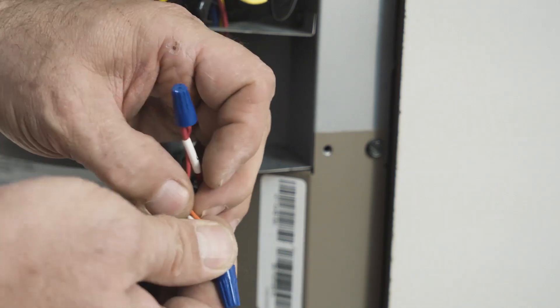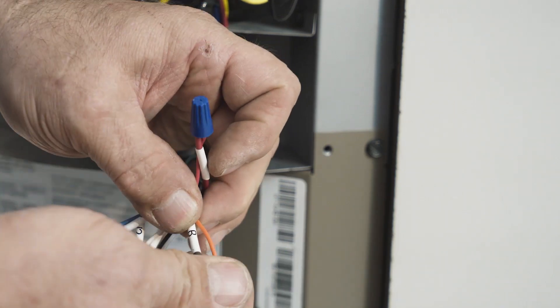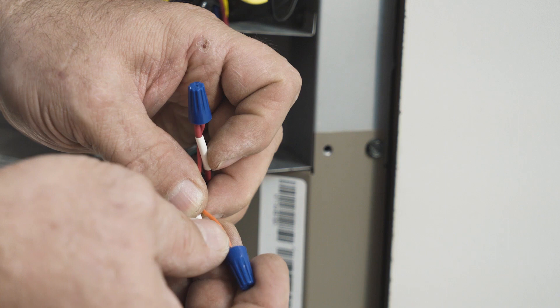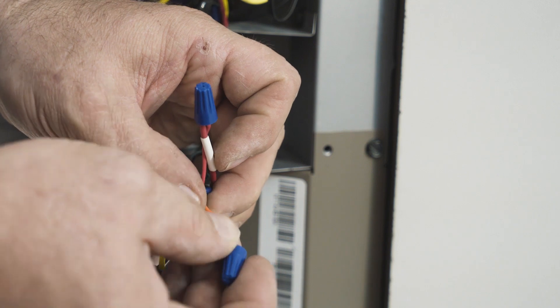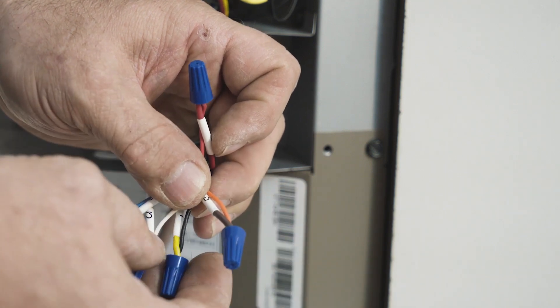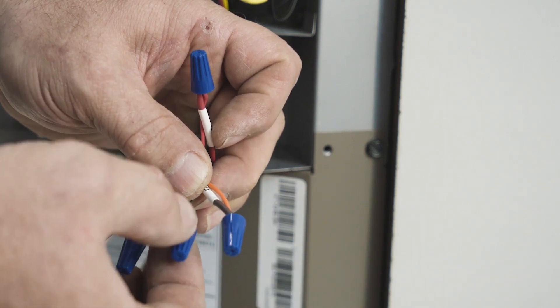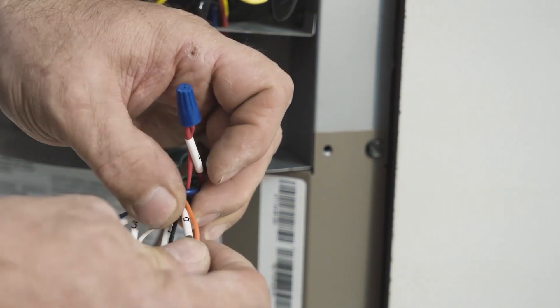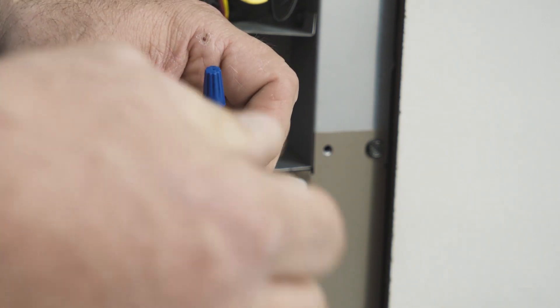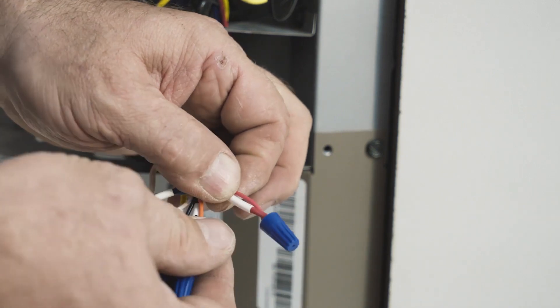The B wire here energizes the reversing valve, so in the call for heat it will energize this one and the B to bring the heat on. R is a power feed to the control board.